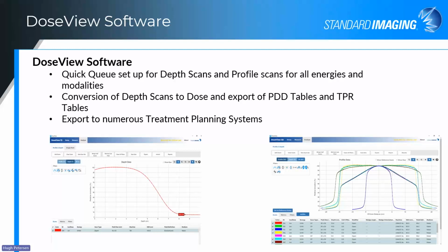So there's not a whole lot of post-scan processing necessary, but those tools to do so are there. And then we have the conversion of the depth scans to dose, which I didn't touch on, but it's a one button touch because you put in the inner diameter of the chamber, so it's a quick conversion there as well. And you can export that to PDD tables and also do calculated TPR tables as well, or to just about all the main treatment planning systems out there also.